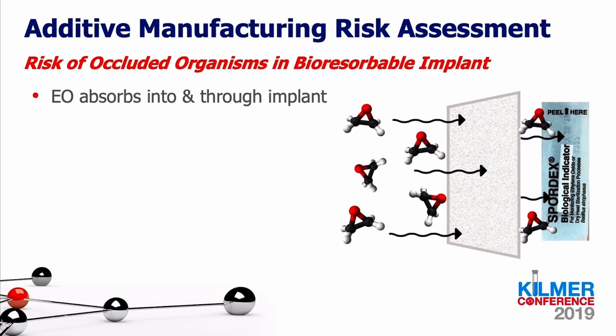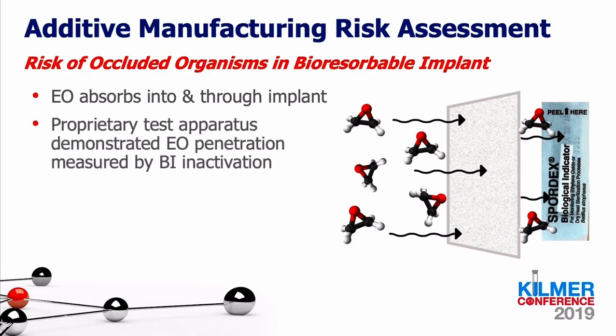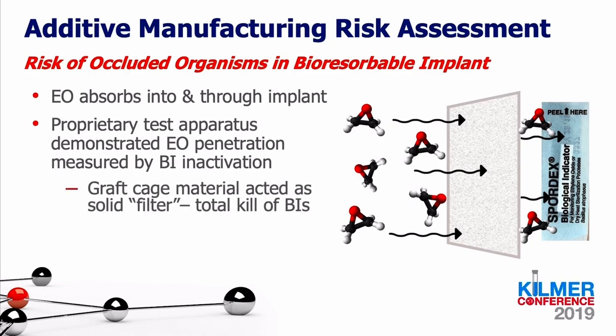So it doesn't have to do with 3D printing in particular, but we did find a way to test this, which is really exciting. The exciting part is that we found that the EO absorbs into and through our implant. So we used a proprietary test apparatus that was designed by one of our colleagues at JJSA Raritan. And through this device, we found that EO penetrated through. We had inactivation of the biological indicators that were opposite the graft cage, which acted as a filter, essentially. It was a solid filter.